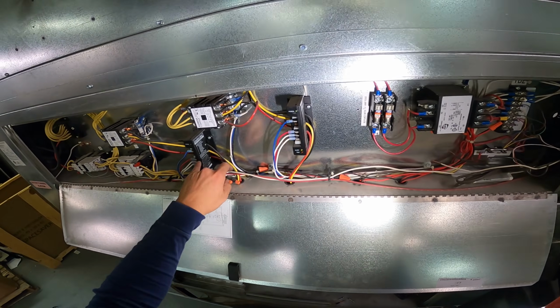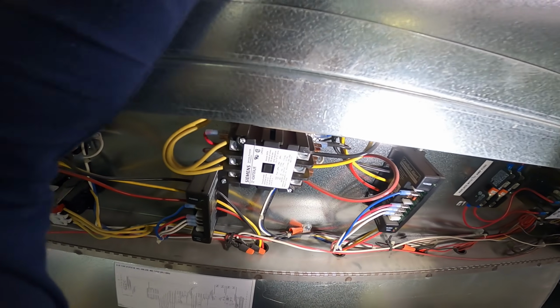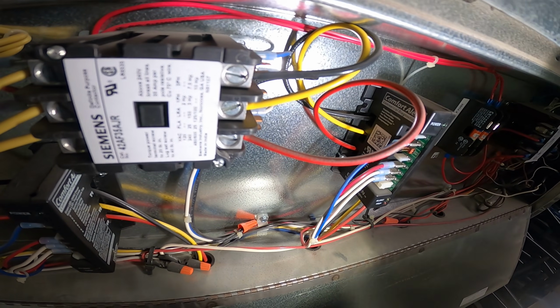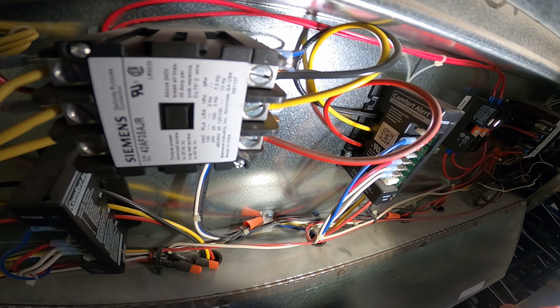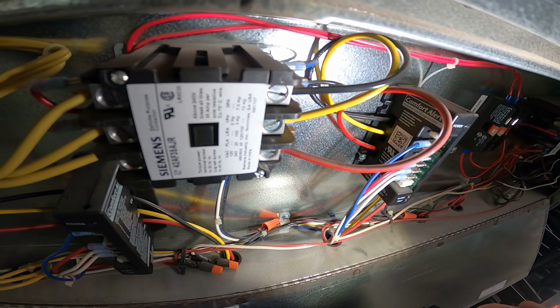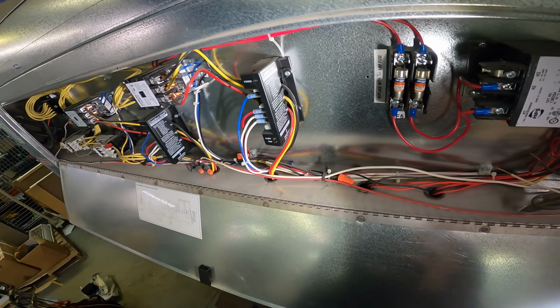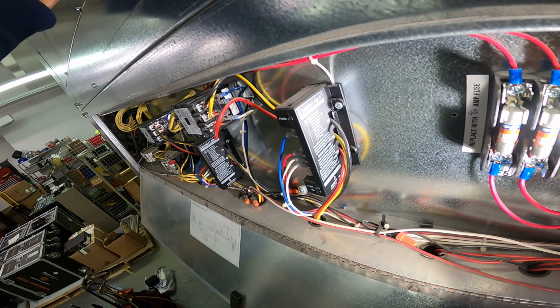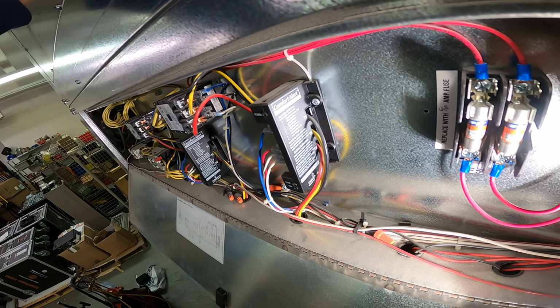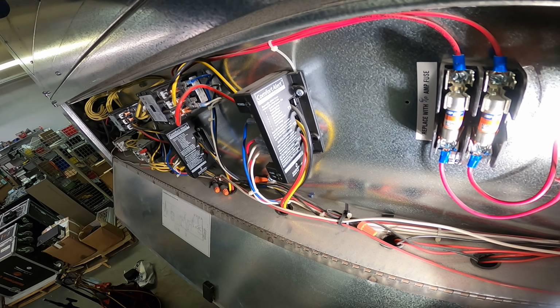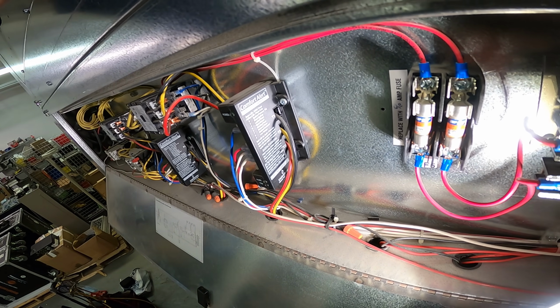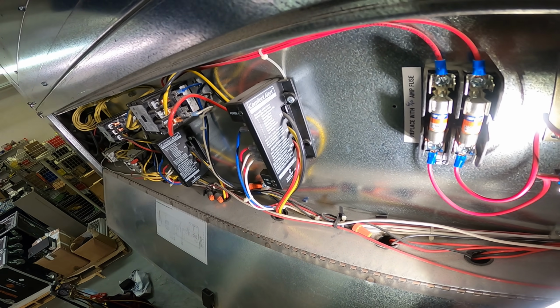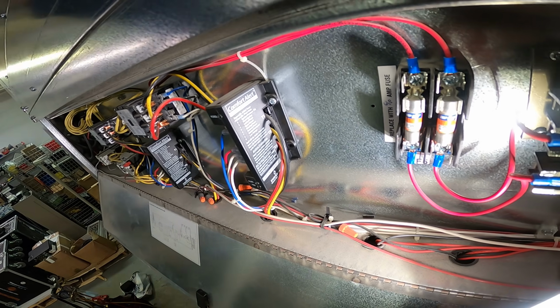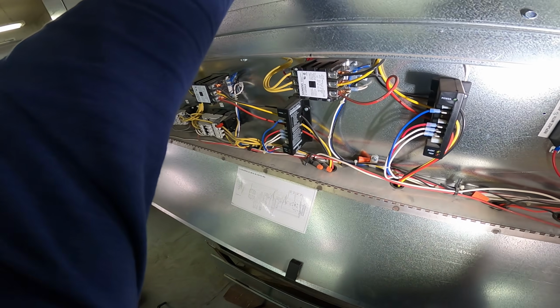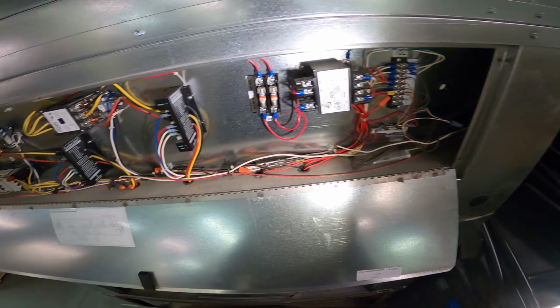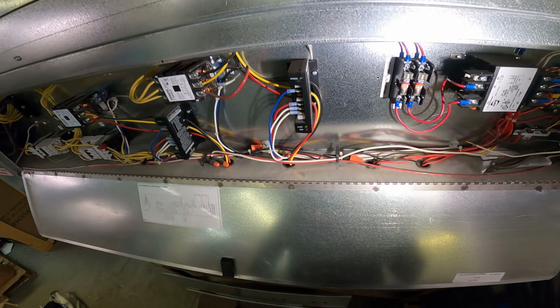These two components here, since we have two compressors, this is like some type of phase monitor, and it says it actually provides diagnostics and protection for 3-phase Copeland Scroll compressors. So it's a safety thing. There are some LED lights here, and depending on the flash codes, it signals a different issue. Let's say it flashes twice, system pressure tripped. 3 flashes would be short cycling, 4 locked rotor, etc. So that's pretty cool. Kind of helps you to troubleshoot, but sometimes this thing itself is the problem.